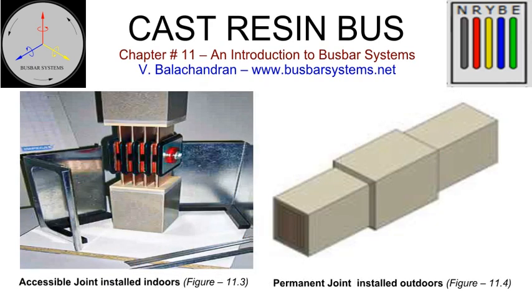When a cast resin bus is installed indoors, a site joint assembly makes the connection between the two adjacent sections. The joint is boxed in a site-assembled, insulating box. The mating surfaces of the box and cast resin bus body are sealed with a gasket to deliver the desired degree of protection. These joints can be accessed and maintained. It also helps during the installation and removal of sections where there are space constraints for the movement.